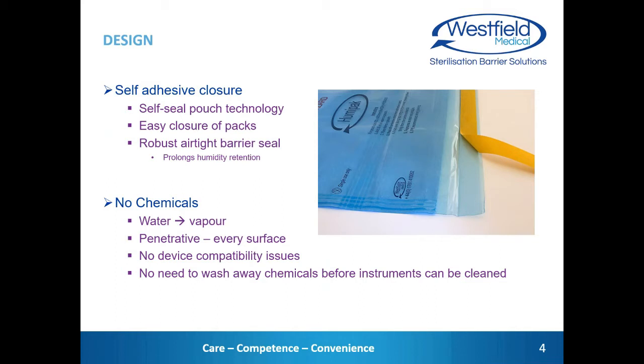So the water is added to the pouch. That then becomes a very significant amount of water vapour. That water vapour then contacts every surface of the instrument in the pack and even penetrates into the box joints and lumens. There are no surface tension limitations as there are with liquids and gels to wet out onto those surfaces. There are no pre-treatment chemicals to buy, no need to make sure that every surface of every instrument is covered with sprays or gels, and no need to wash away those pre-treatments before the instrument can be cleaned.